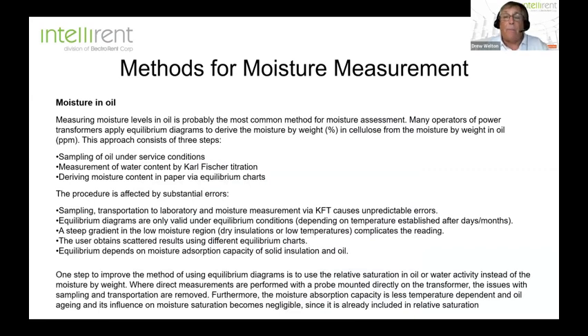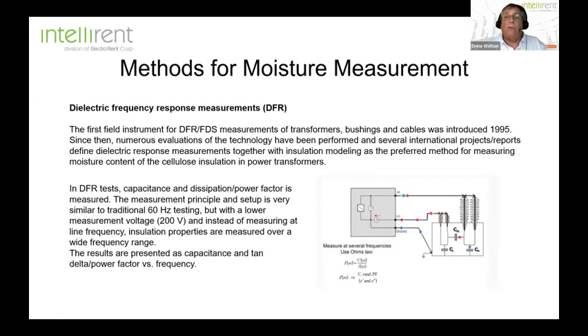Now, there's a couple of ways to check for moisture levels, and of course, this is measurement in the oil, which we know can be somewhat inaccurate and may even give you a false indication at a higher level. So what is the new technology that we use? Around 1997, the University of Stuttgart came out with a process called frequency domain spectroscopy. They changed the name to dielectric frequency response because it's easier to say. Basically, it's a power factor or tangent delta measurement over an extremely wide frequency range.